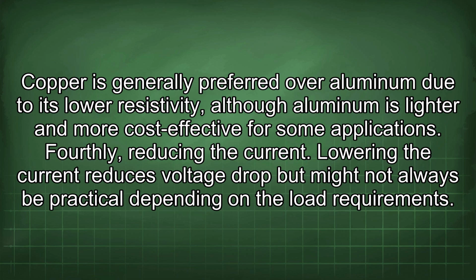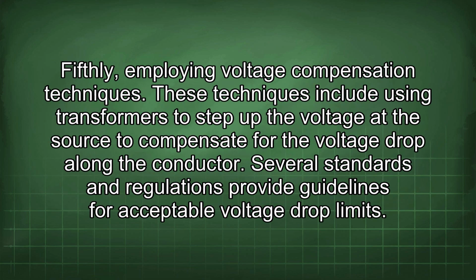Fourthly, reducing the current. Lowering the current reduces voltage drop, but might not always be practical depending on the load requirements. Fifthly, employing voltage compensation techniques. These techniques include using transformers to step up the voltage of the source to compensate for the voltage drop along the conductor. Several standards and regulations provide guidelines for acceptable voltage drop limits.